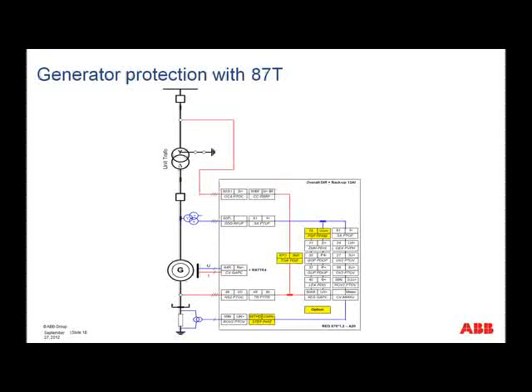This once again shows really pretty much the same protection functionality as what we saw before, but now instead of using an 87G, the current is taken from the other side of the step-up transformer, and so now we get an 87O or overall differential function. Now the 87O function itself is pretty much an 87T really, because of the transformer that is now in zone, and so has to really handle all the same issues that a 87T function can handle.